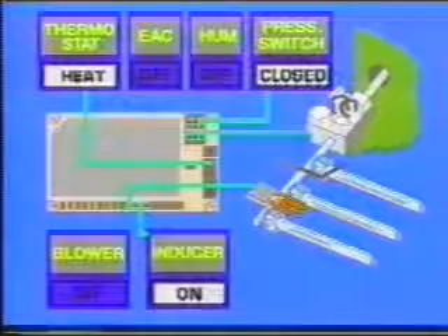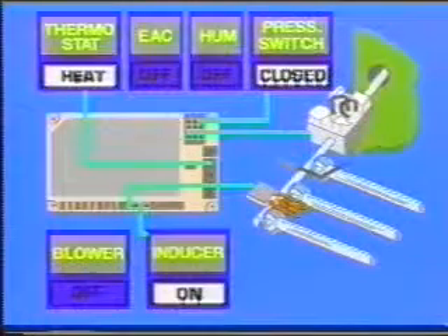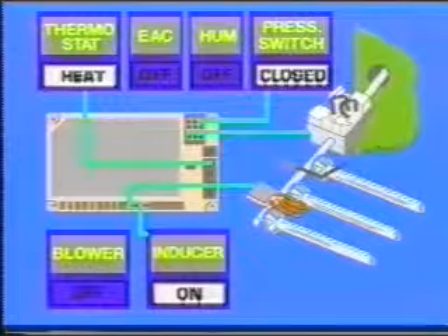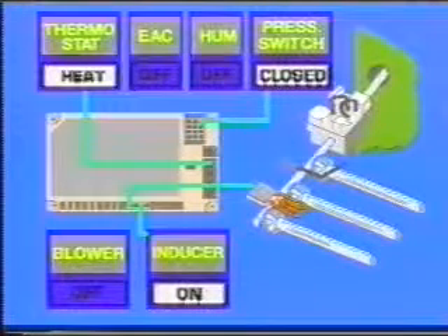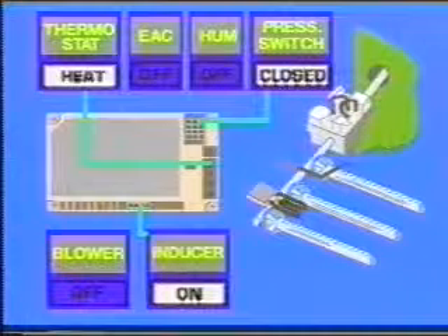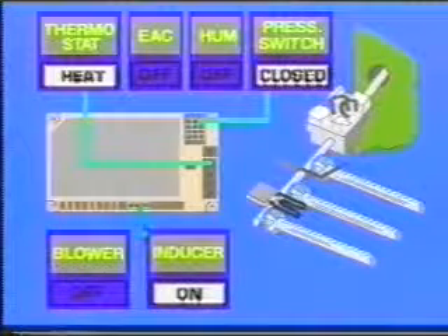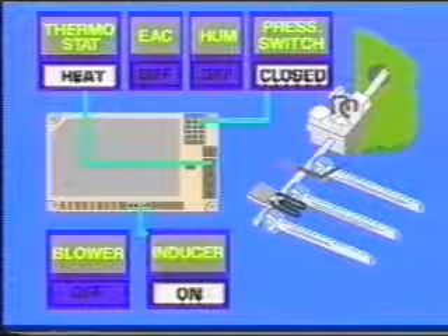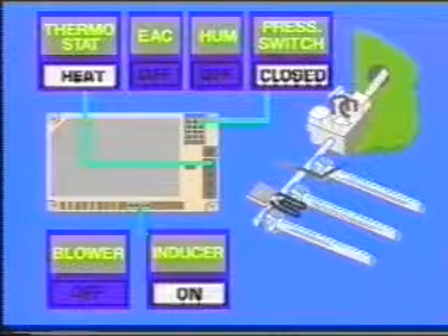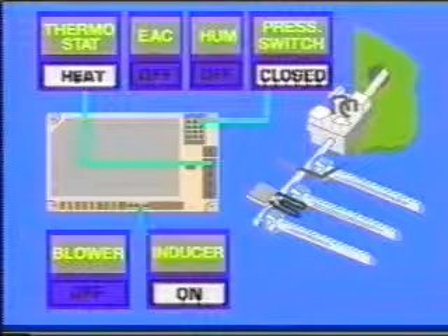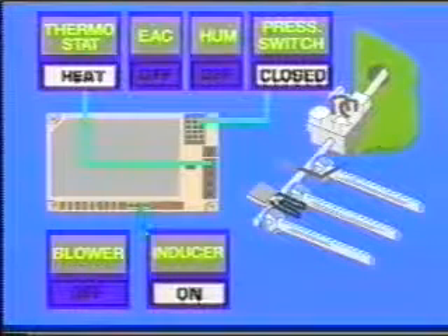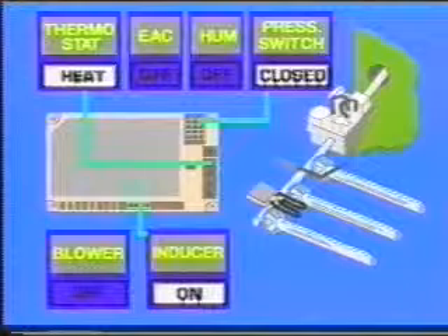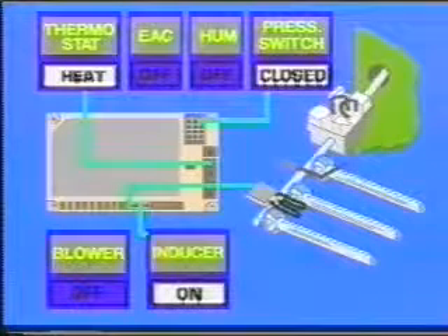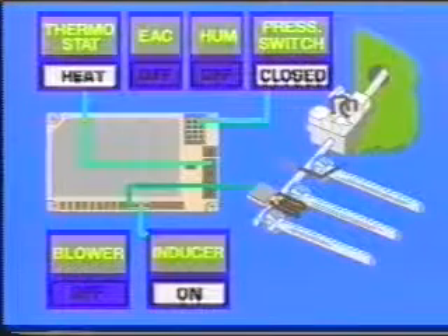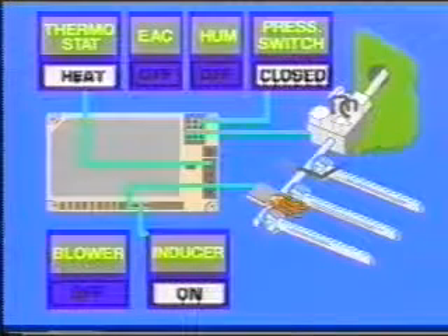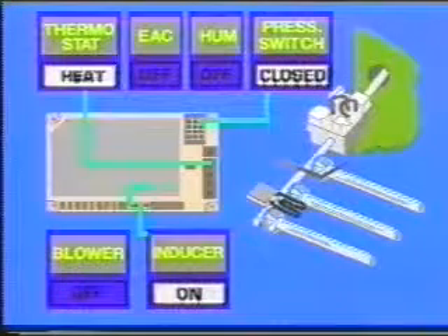If on a try for ignition the module does not prove ignition within the trial for ignition period, the gas valve will close. The module will then go into a retry mode. In the retry sequence, the inducer will be powered for a 30 to 90 second interpurge following a failed ignition attempt. The interpurge time varies with the module version. At the end of the interpurge, the ignition sequence is restarted with an additional 10 seconds of igniter warm-up time. If this attempt is unsuccessful, a new retry sequence is initiated.